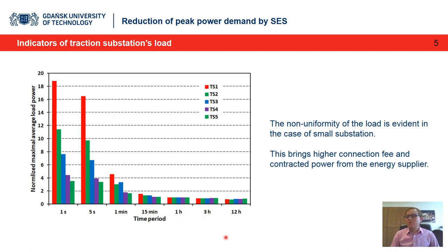Why is this important from a practical point of view? It has two effects. The first problem it causes is that we need to oversize a lot of parts of the traction substation, because even if we consume an average of around 50 kilowatts on a 1 hour or 3 hour scale, on a 1 second or 5 second scale the load value can be 10 or 20 times bigger, so 500 kilowatts, and elements like the AC switchboard need to be dimensioned for this bigger load value.